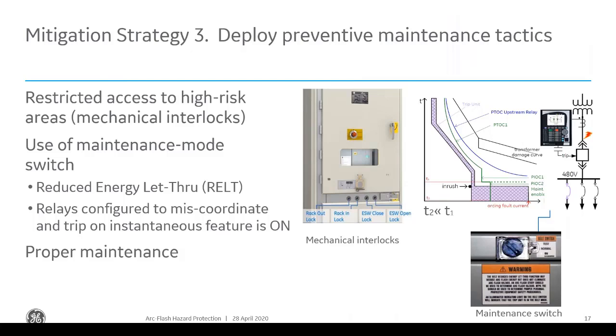Mitigation strategy 3: deploy preventive maintenance tactics. One of the more effective is to reduce the access to the high-risk areas. So interlocking systems can be set for mechanical parts to prevent improper operation. For example, a circuit breaker cannot be closed when it's between the connected and test/disconnect position. Some switchgear is equipped with interlocking systems. Most in today's market should be equipped with these interlocking systems.